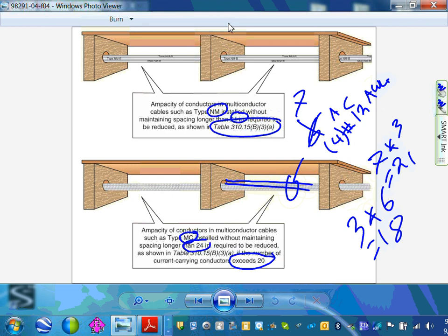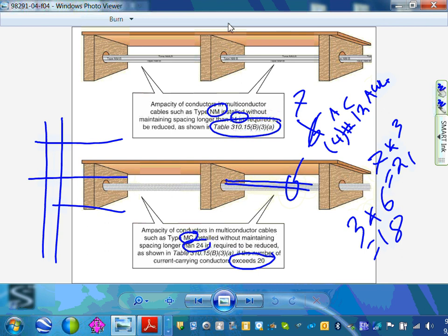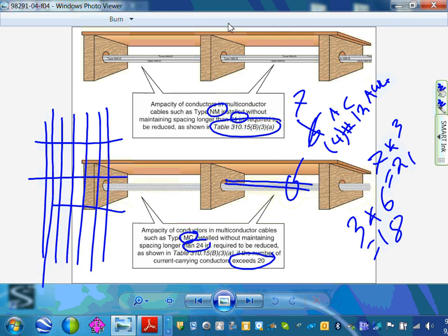If you have a rack or something and you put them like these, with 1 space in between them, and not grouped, sitting side by side on a rack or whatever, then you don't have to do anything. That's when you bundle them. You've seen them, guys. They bundle them. Sometimes they grab them, hold them. Then you can't put more than 6. And 6 is a lot.